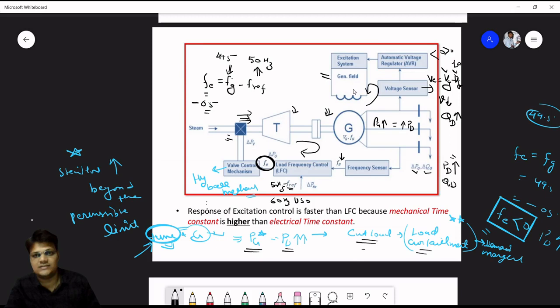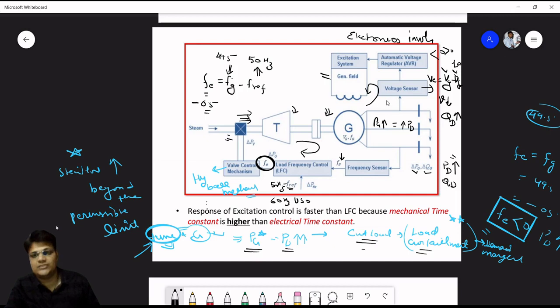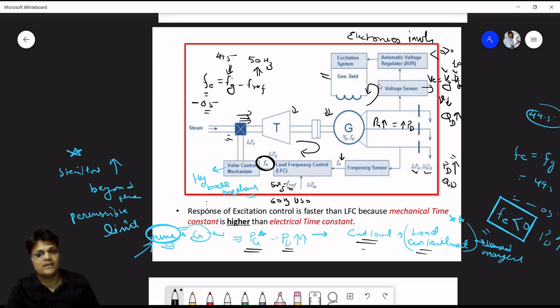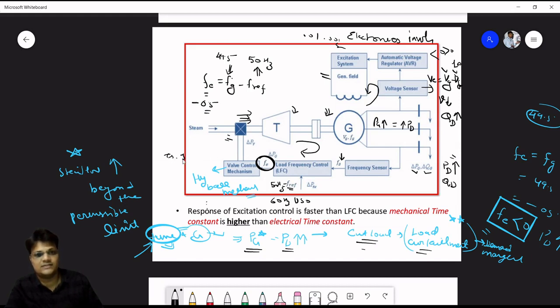The excitation system involves electronic circuits, while the LFC loop involves mechanical parts. The mechanical time constant is higher than the electrical time constant. Therefore the excitation voltage control system is faster — with a time constant of 0.01 or 0.001 seconds — while load frequency control is slower, with a time constant of 1 or 2 seconds.